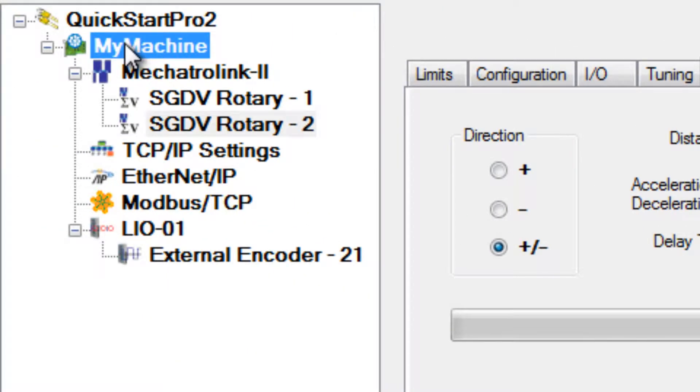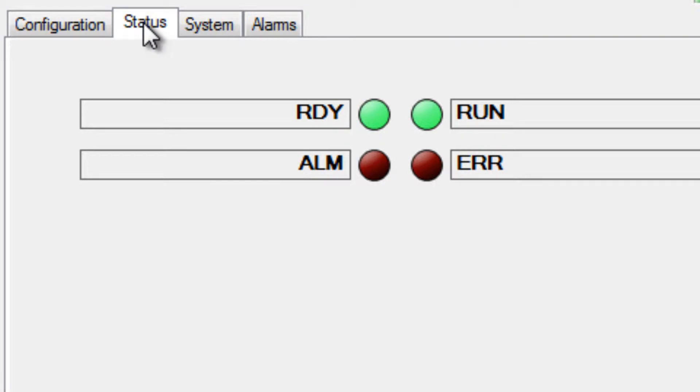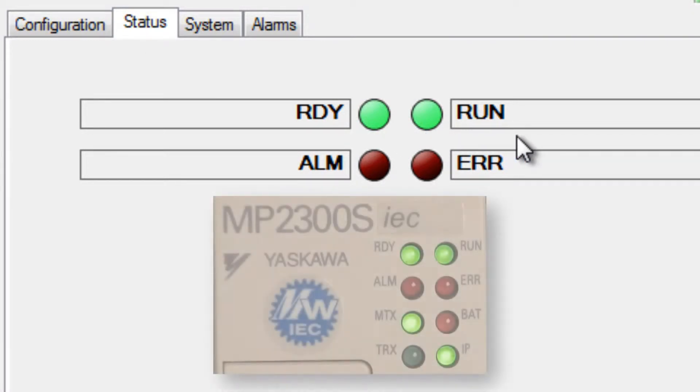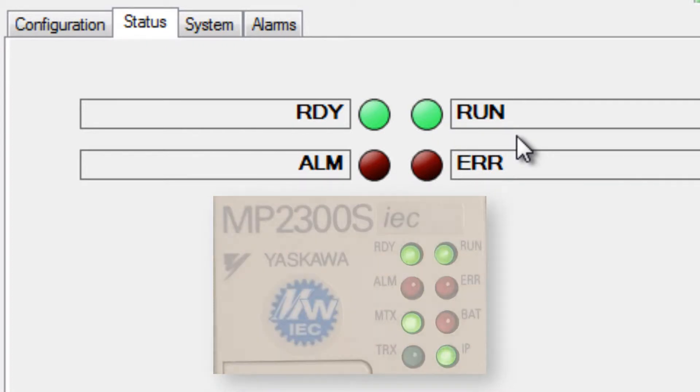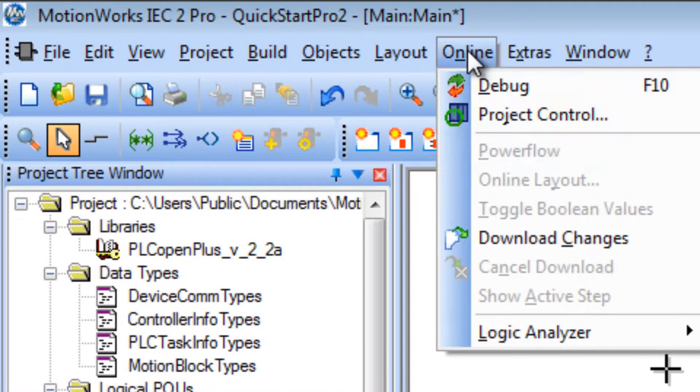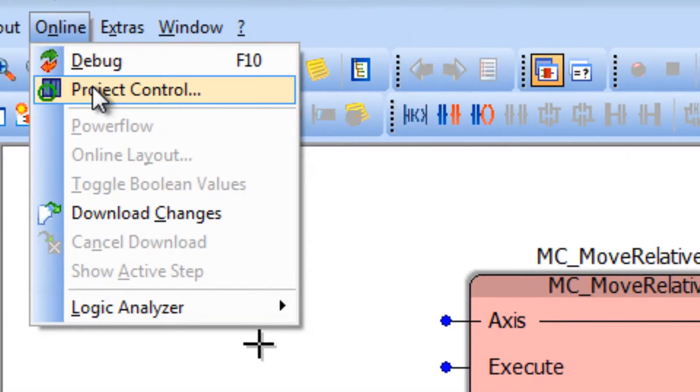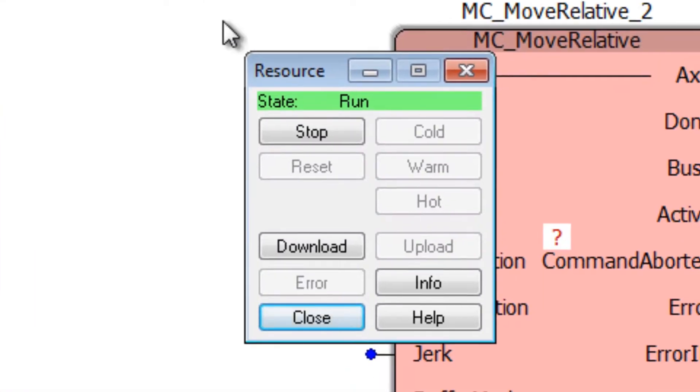Go to my machine and the status tab to see if the run LED is on, indicating run status. This is the same as what you'd see at the front panel of the controller itself. Since the run light is on, I'll temporarily stop the controller in the programming interface by going to the online menu, project control, and in the resource window, click stop.